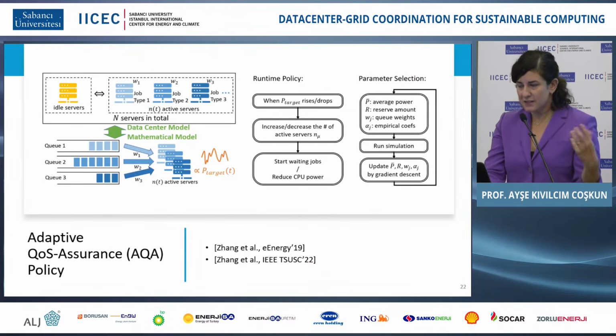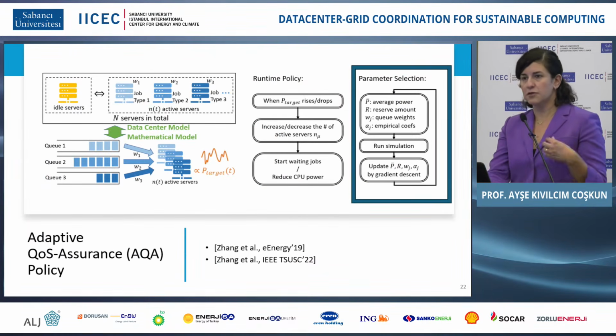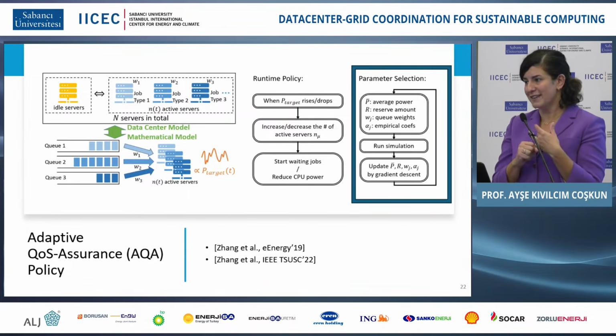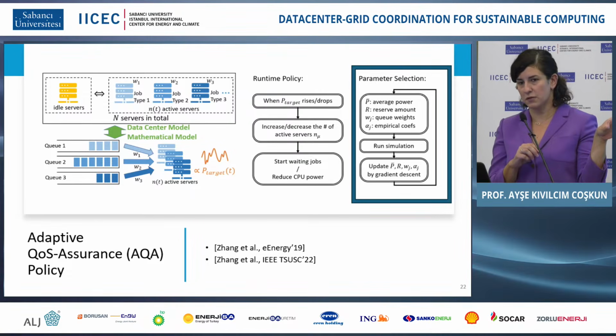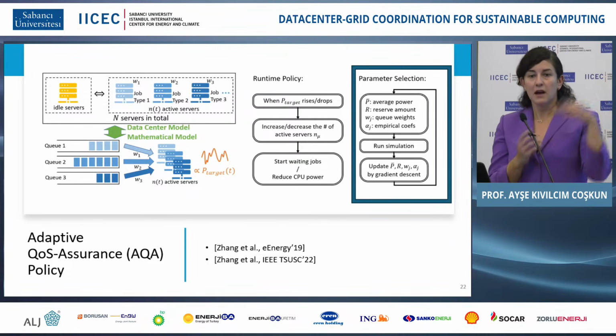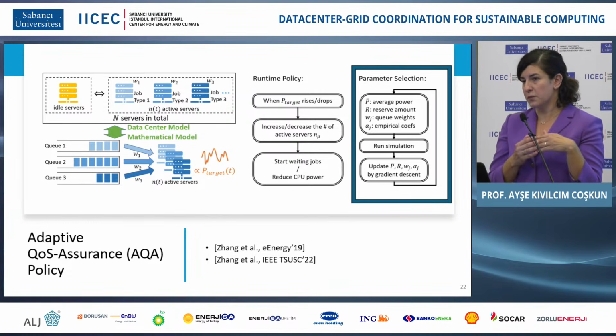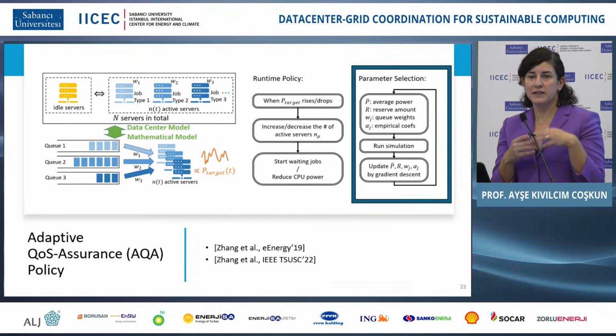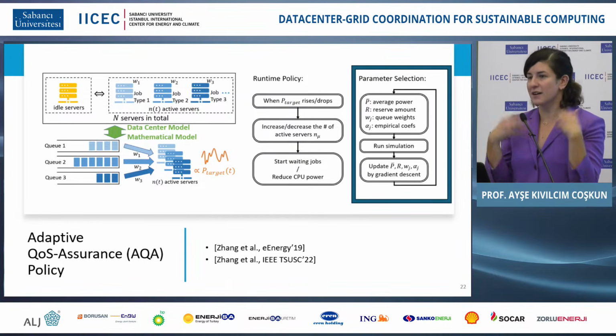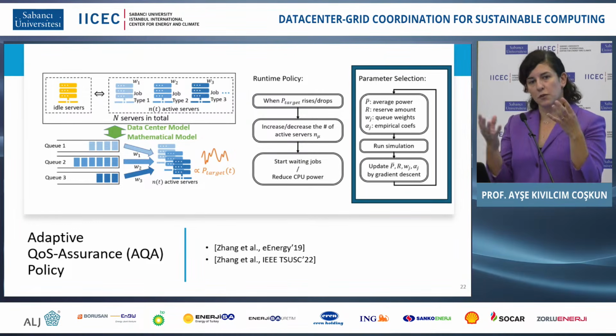So our secret sauce to making this happen is to first run algorithms to do parameter selection for how much average power do I need to meet these statistical quality of service constraints. Do I need 10 megawatts? Do I need 15? How much regulation can I provide? Can I provide just 1 megawatt or 5 megawatts of regulation capacity? Because this is going to be the flexible capacity I offer to the grid. First, we run optimization methods for that.